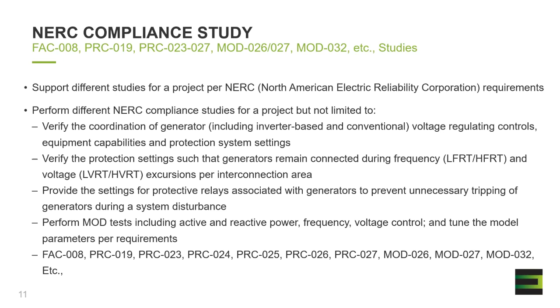Some of this includes performing voltage ride-through and frequency ride-through settings, as well as performing site testing to ensure that the reactive power capabilities of the projects are meeting the ISO requirements, and the reactive power, frequency, and voltage control are tuned as per the NERC requirements. And all these reports are submitted and kept on file in case the project gets audited. These are reviewed. If there are compliance issues, then projects are penalized heavily by NERC.